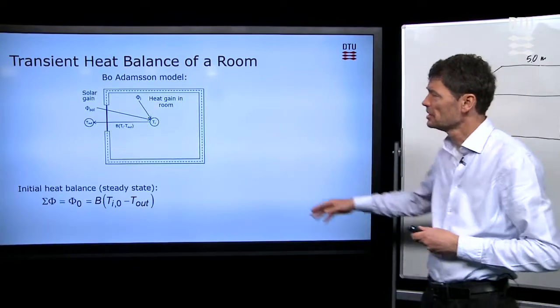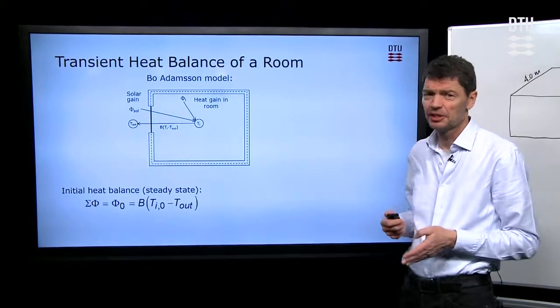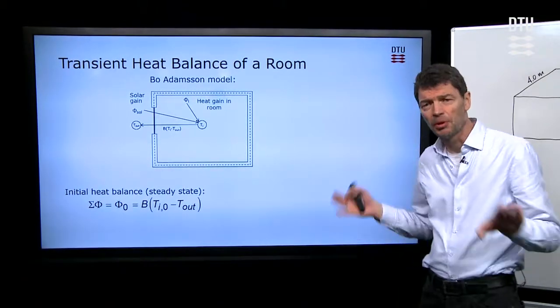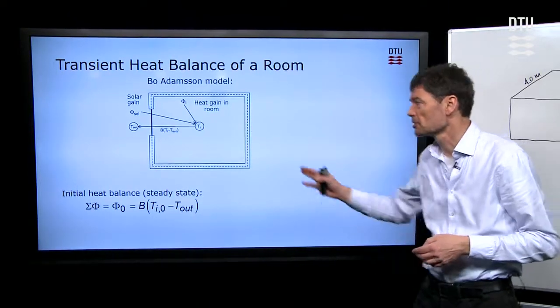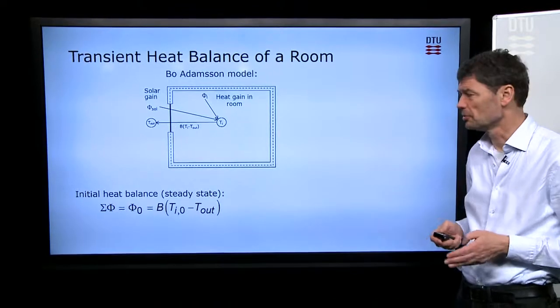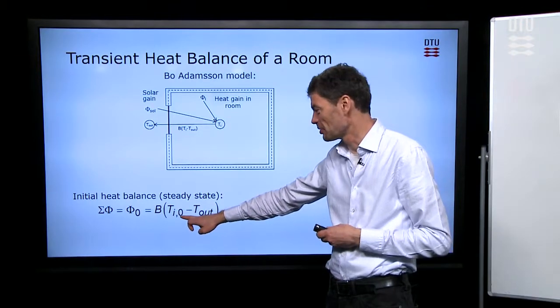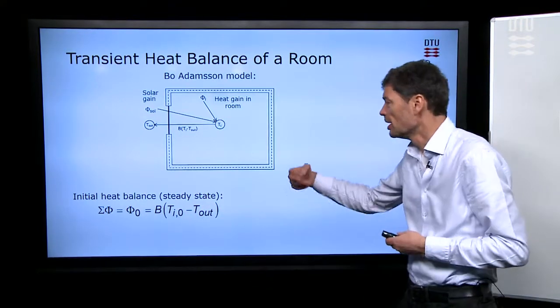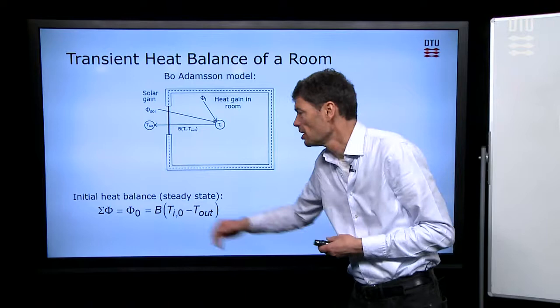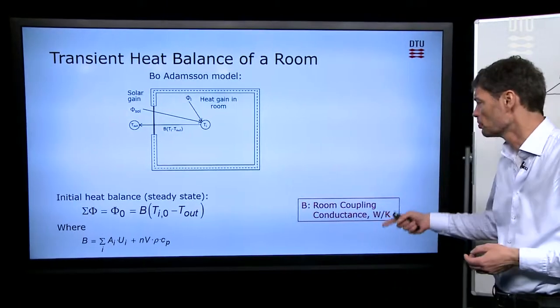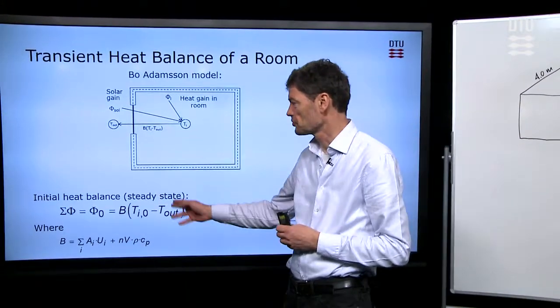What we'll talk about is the heat balance for a room that we have here on the picture. Initially we set up some things where the room is in thermal balance with heat supply, heat gains in the room, and also heat losses to the outside. This balance is expressed down here, that we have initially a temperature within the room at time zero, and we have another temperature outside of the room, and the difference between those two temperatures multiplied with a room coupling conductance, a coefficient that couples heat transfer between the room and the outside.